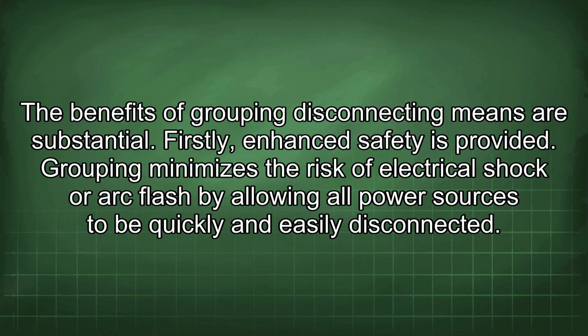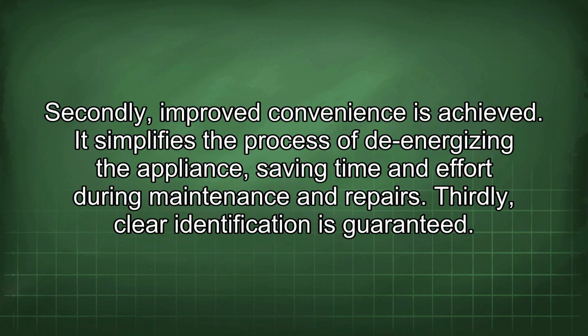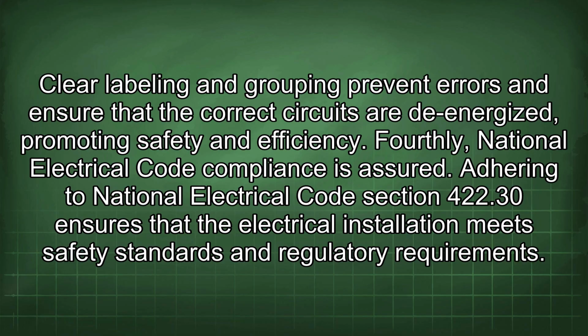The benefits of grouping disconnecting means are substantial. Firstly, enhanced safety is provided. Grouping minimizes the risk of electrical shock or arc flash by allowing all power sources to be quickly and easily disconnected. Secondly, improved convenience is achieved. It simplifies the process of de-energizing the appliance, saving time and effort during maintenance and repairs. Thirdly, clear identification is guaranteed. Clear labeling and grouping prevent errors and ensure that the correct circuits are de-energized, promoting safety and efficiency. Fourthly, National Electrical Code compliance is assured. Adhering to National Electrical Code Section 422.30 ensures that the electrical installation meets safety standards and regulatory requirements.